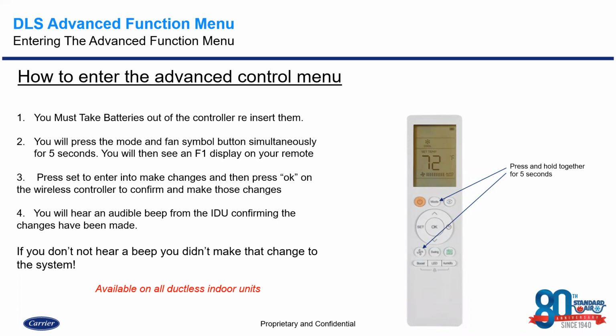So first, we want to make sure that not only do we take the batteries out of the wireless handheld remote controller, hit the on and off button to clear the screen, but we also want to make sure that we power cycle the entire system itself. So shut everything off either at the breaker or before your disconnect, wait for 30 seconds, plug it back in. At the same time, make sure you put your battery back in your wireless controller, and then you're going to press the mode button and the fan symbol button together simultaneously and hold for 5 seconds.